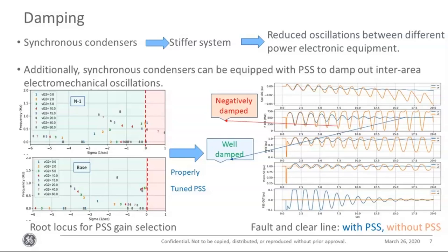But at Energy Consulting Group, some of my colleagues have worked on a project where the synchronous condensers were equipped with a PSS to damp out the inter-area mode of oscillations, which the synchronous condensers do not necessarily participate in, with the two sets of machines interacting with each other. So that involves designing the PSS, and tuning the PSS involves a lot of small signal stability studies, where you have to look at the gain margin, phase margin, and root locus.